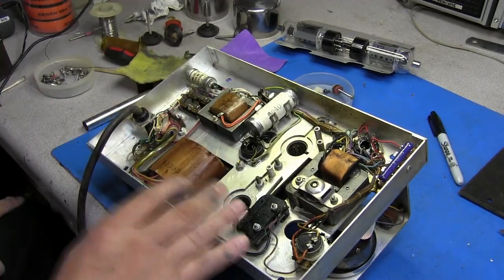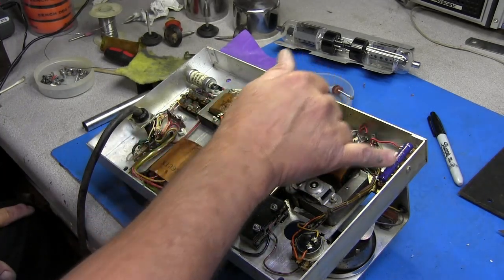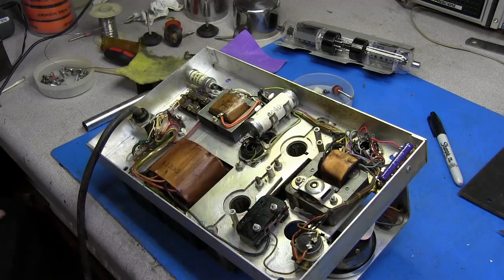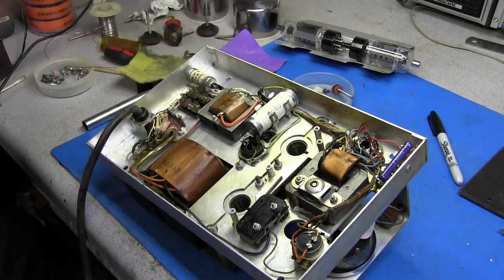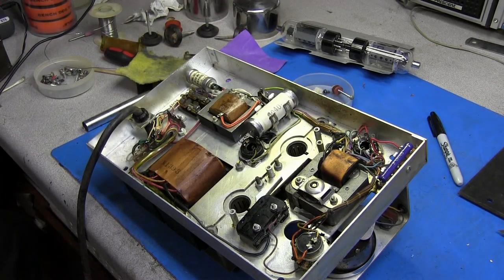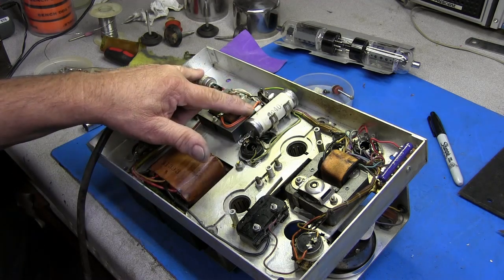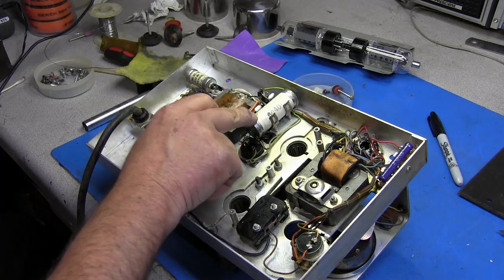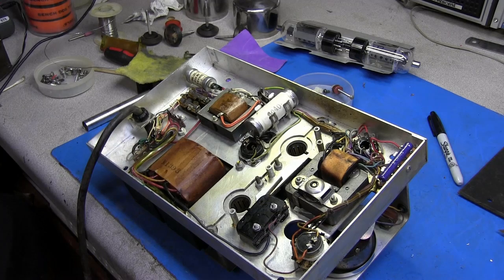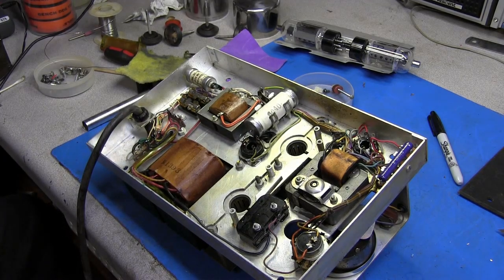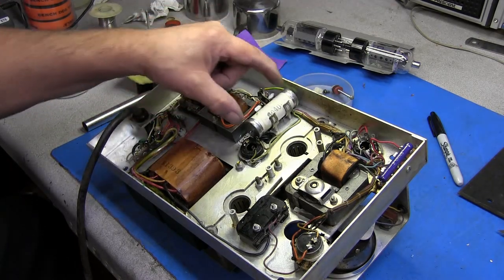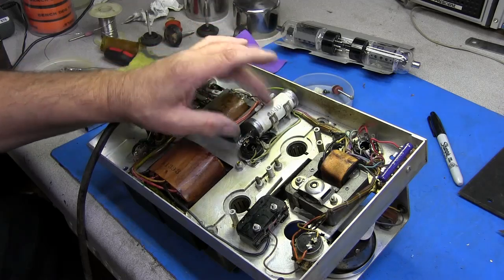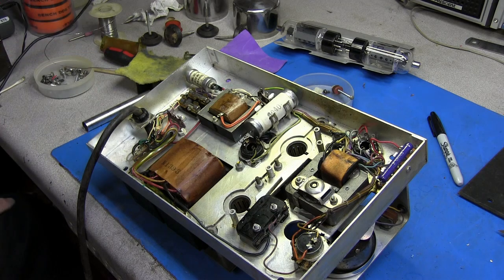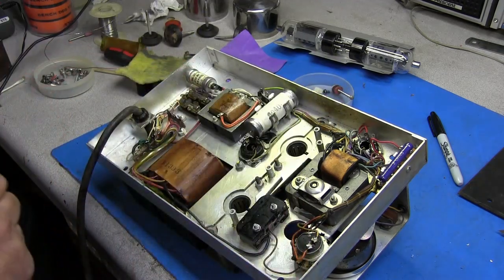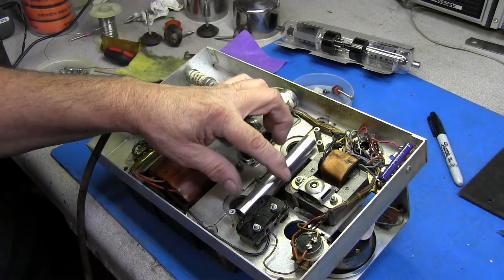Guys, I've been doing a lot of cleaning mostly, and cleaned the switch, replaced this 5-ohm 10-watt resistor with a Sprague 5-ohm 10-watt resistor. This capacitor appears to be okay. I'm going to see if I can order 2 new capacitors and go ahead and just replace them. I don't know what kind of luck I'll have finding 0.015s at 3 kilovolts. But I'll look around and see what I can come up with. I don't have the protective covering on this, but I've got it sitting in here, snapped in place, put back in the circuit just for testing purposes. I've cleaned the micro switch. The interlock tube has been cleaned. So I can get that back down in place.